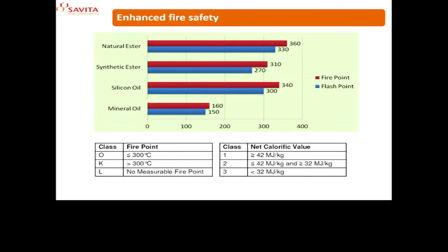Then of course enhanced fire safety, because ester fluids are known as K class fluids. As per the definition in IS 13503, K class fluids are oils having a fire point above 300 degrees Celsius. Ester oil falls under that category, whereas mineral oil, at around 160, is O class. So K class fluids offer far better fire safety to your transformer. They are approved by FM and UL, and the certification says they are 5 to 6 times less flammable than paraffinic based mineral oil.